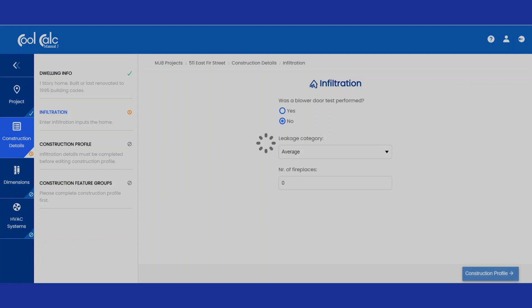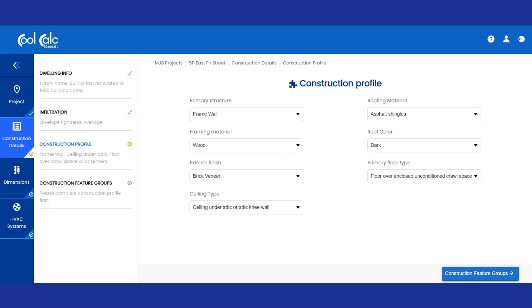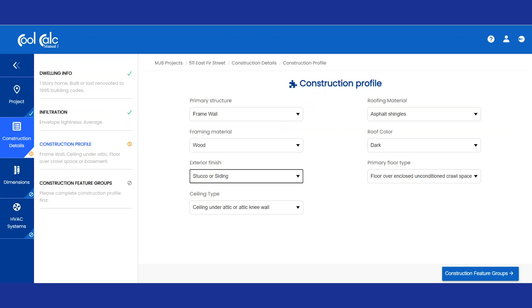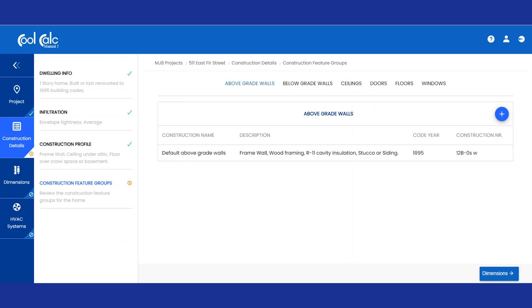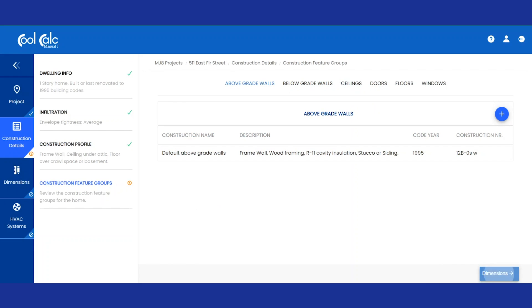Since 1995, some of this information could have changed. So if your siding isn't brick, make sure that you change it to what you've got. If you have a metal roof instead of an asphalt roof, make sure that you click that. This is where this program gets really great — in order to do a proper Manual J, you have to measure walls, windows, attic space, insulation, and a lot of things that you may not know. But this program takes into account all of the codes that were required in the year that your home was built.